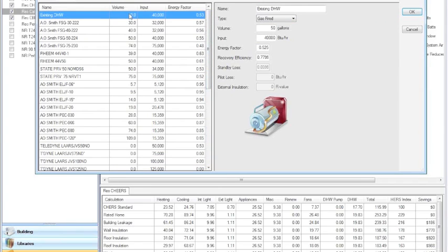So I would call this new DHW. And I would give it the current code efficiency level of 0.575. Okay, so that is a new water heater. So putting the blanket on the older water heater will bring it up to the efficiency level of 0.575. And so what you're doing is you're telling EnergyPro that that water heater efficiency has now been increased by the reduction in blanket losses that are associated with it. So that's actually a pretty easy one to do. Okay.